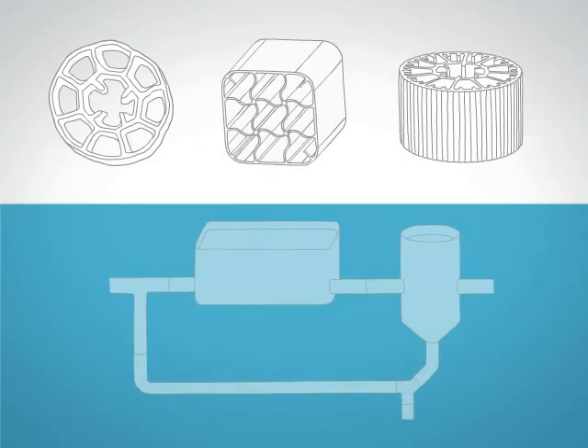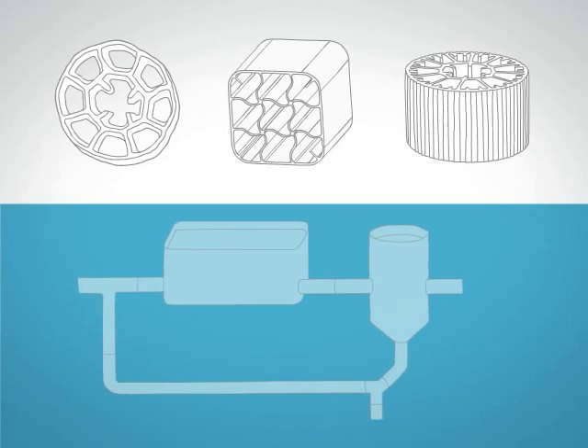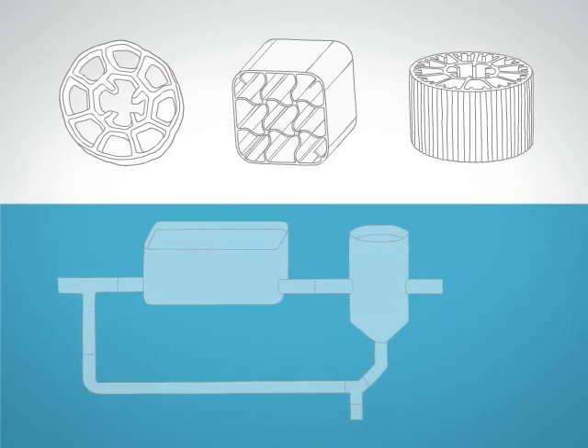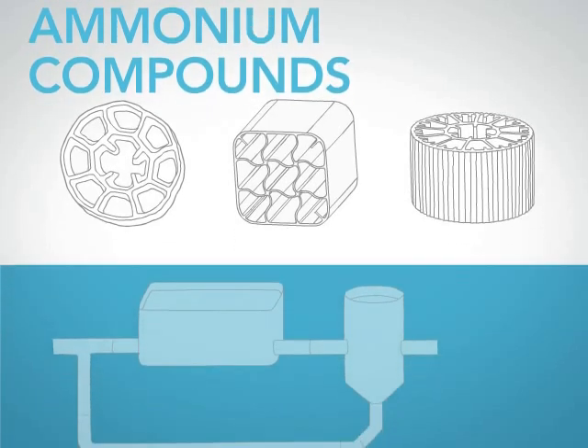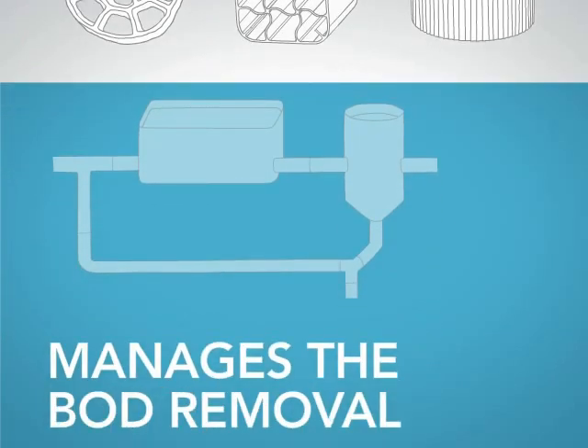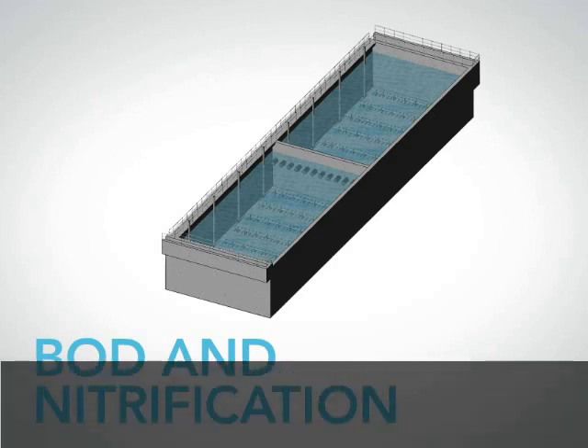IFAS combines the best of two processes: activated sludge and fixed film. The fixed film process oxidizes ammonium compounds, while the activated sludge process manages the BOD removal. Alternatively, the reactors can be configured to have BOD removal and nitrification in both fixed film and the suspended growth phases.